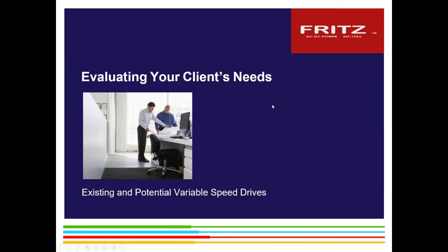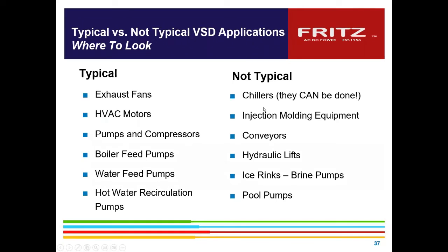For example, some of my customers had put drive controls on certain pumps, but they found their power bills really didn't go down, because you need to look at the total acre feet of water that you're getting onto the crop. If you slow it down, it's going to do it at a slower pace. And then also look at the individual pump curves to determine the right spot for that. Again, some typical applications out there: we've done a lot of work on ice rinks and a lot of hydraulic applications.